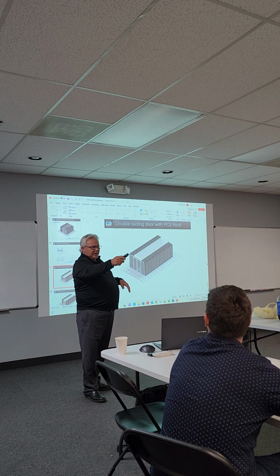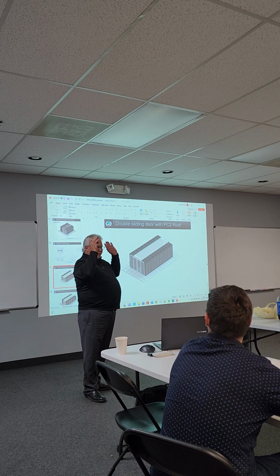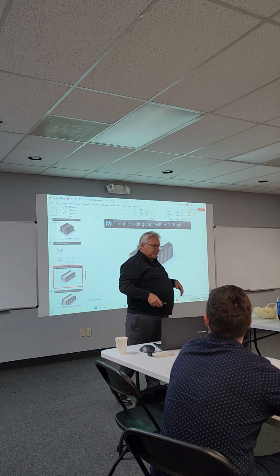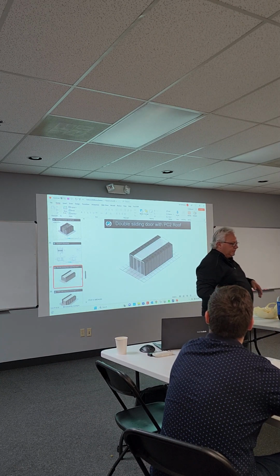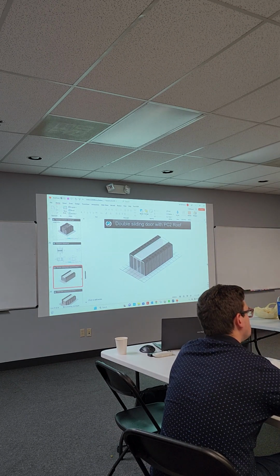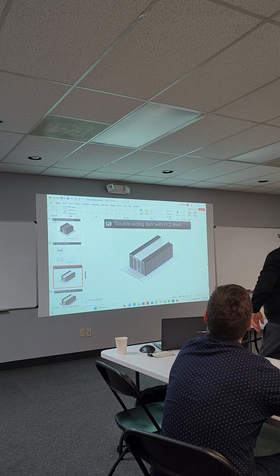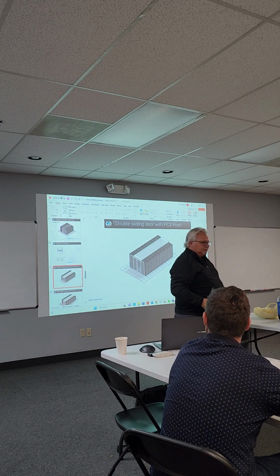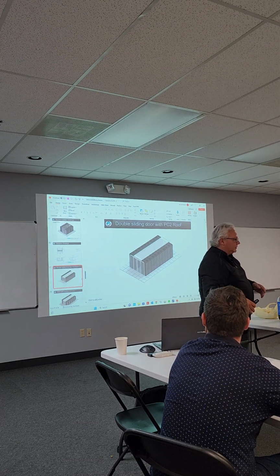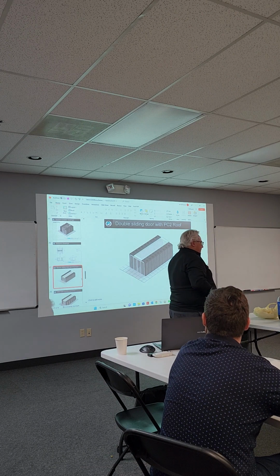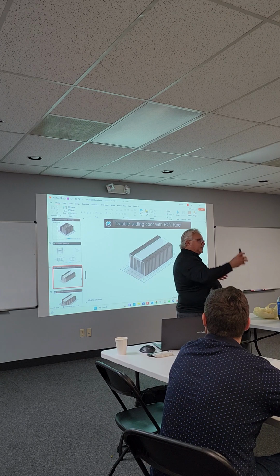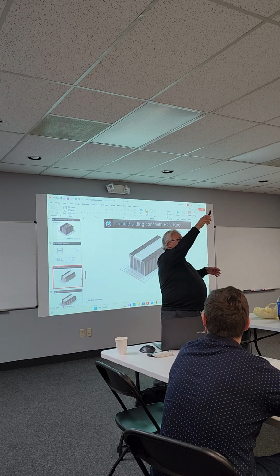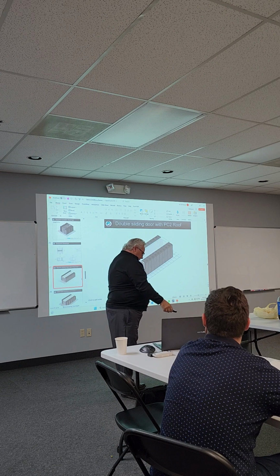So if I had a unit free blowing, and the return is in the front, and there's a piece of equipment 6 foot tall, the air comes shooting out, hits that piece of equipment, and the cold air goes right back to the unit's return. Now the equipment down there isn't getting its proper cooling. So if I could duct that unit, bring it overhead, put some drops in, let that cold air fall - that's the way to go.